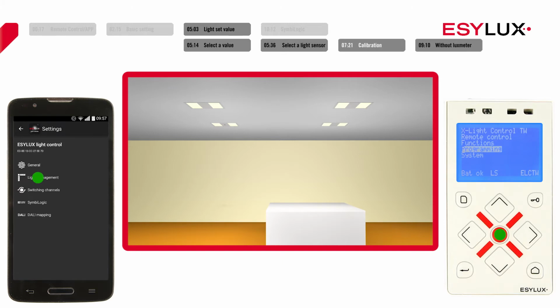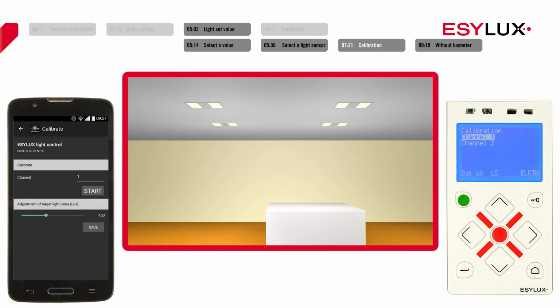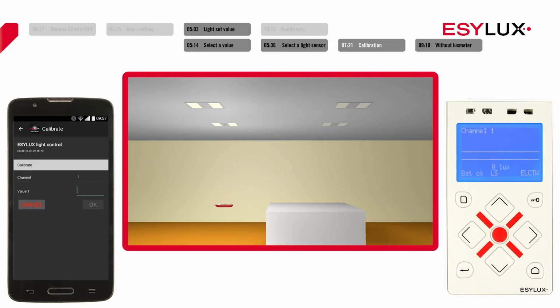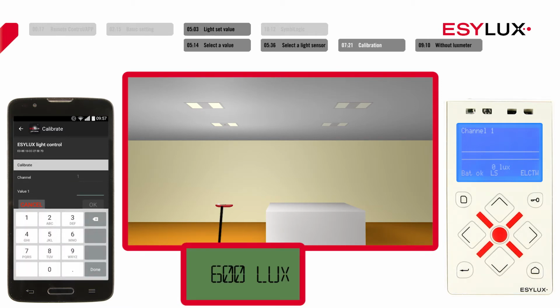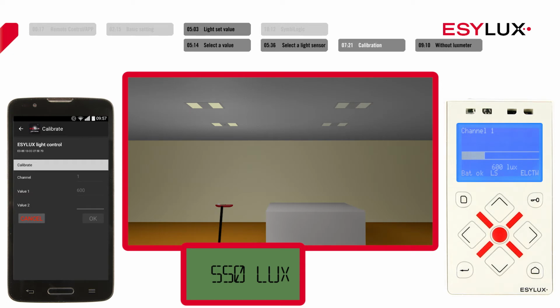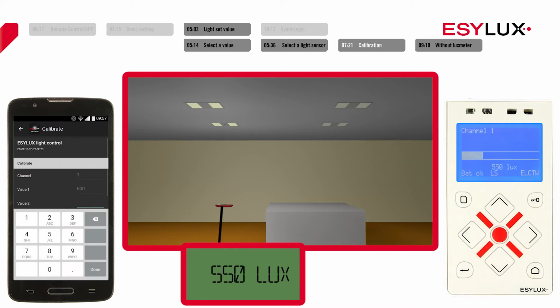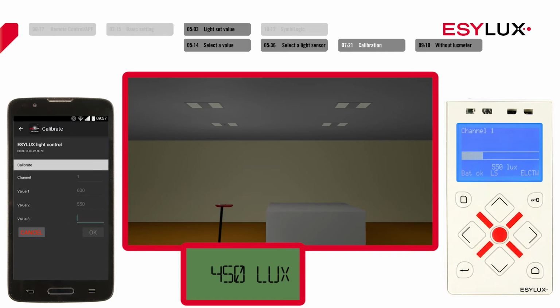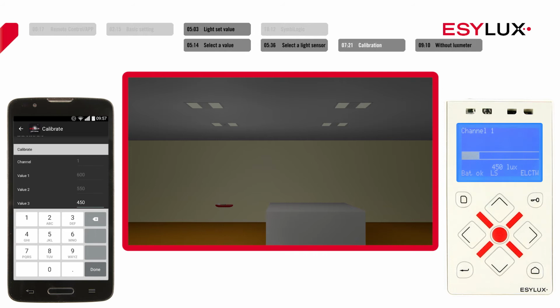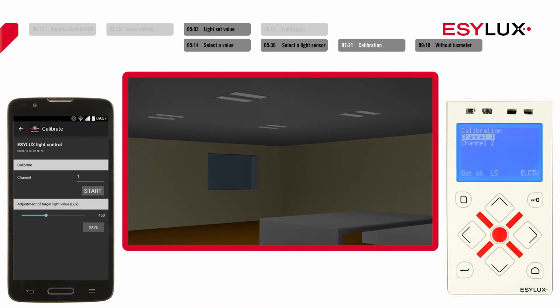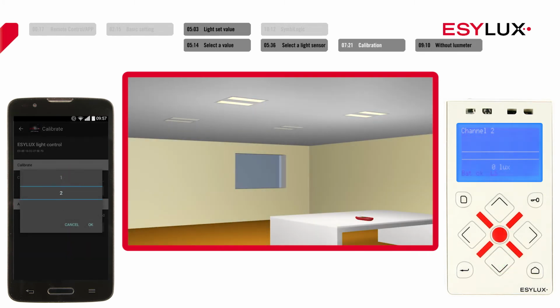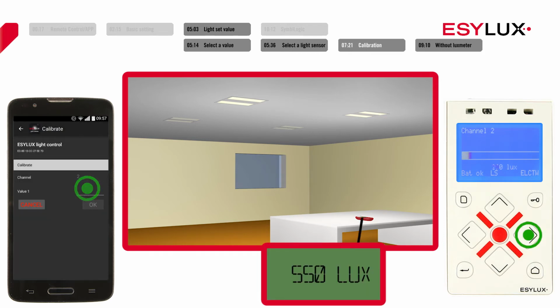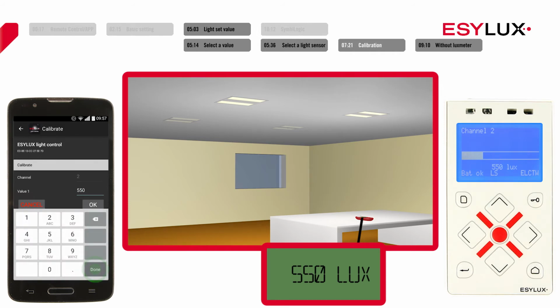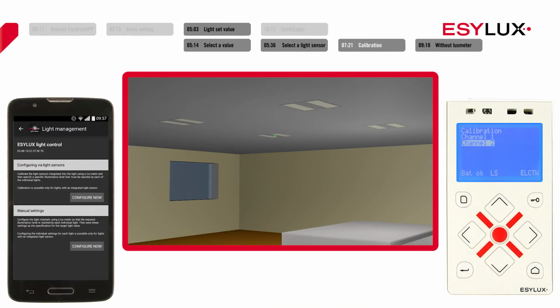Select the first channel. Place the lux meter underneath the light at table height. Transfer the lux value from the lux meter and confirm. The light will now dim slightly. Transfer the new value. The light will switch off. Transfer the third value. The calibration process for the first channel is now complete. Repeat the process for the second channel. The sensors are now calibrated.